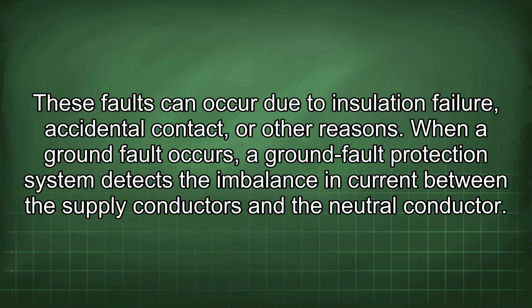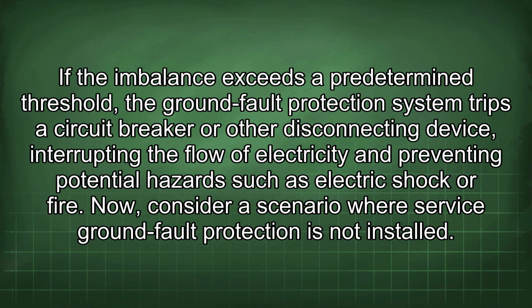When a ground fault occurs, a ground fault protection system detects the imbalance in current between the supply conductors and the neutral conductor. If the imbalance exceeds a predetermined threshold, the ground fault protection system trips a circuit breaker or other disconnecting device, interrupting the flow of electricity and preventing potential hazards such as electric shock or fire. Now consider a scenario where service ground fault protection is not installed.